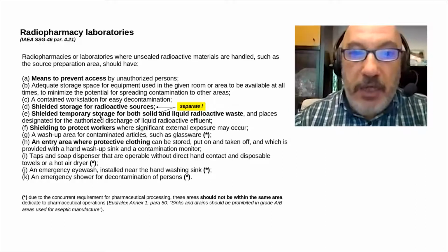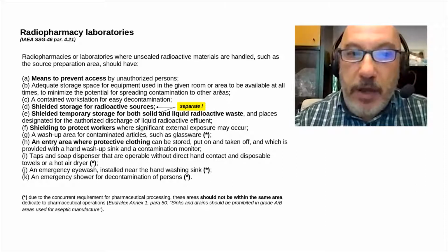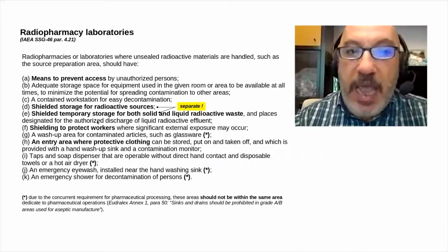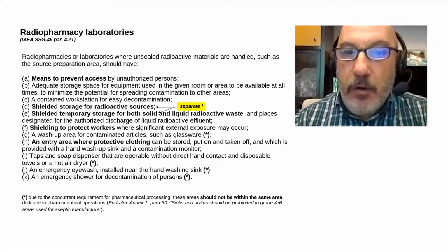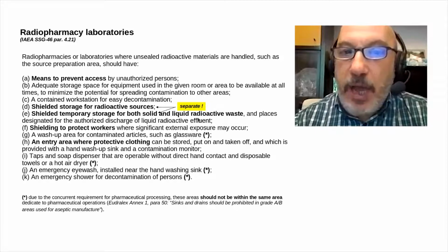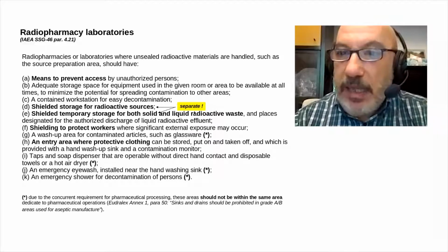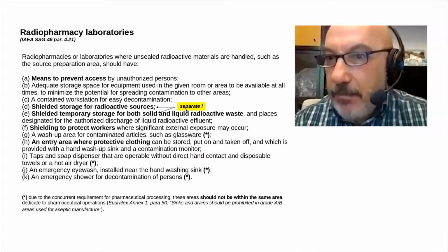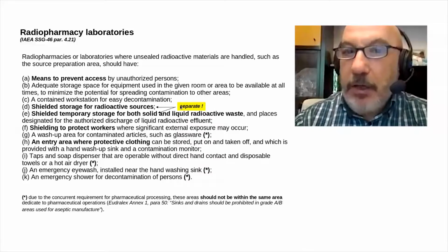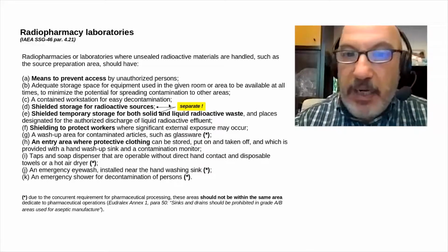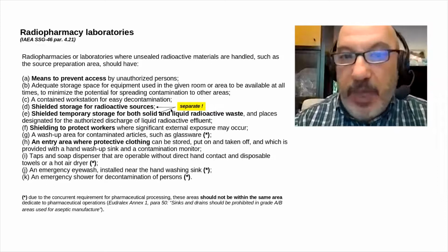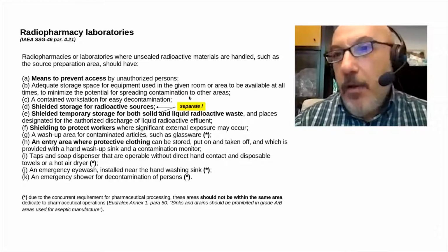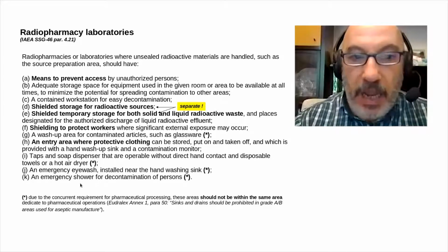Then there should be shielded storage for the radioactive sources, workstations and hot cells for the manipulation, and proper collection of the radioactive waste. It has to be considered that radioactive waste should not be hosted, if not for a very temporary period of time just after the preparation, within the clean area of the laboratory, to get a good separation between clean product and waste.